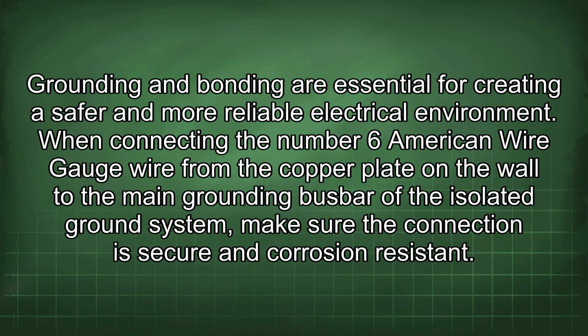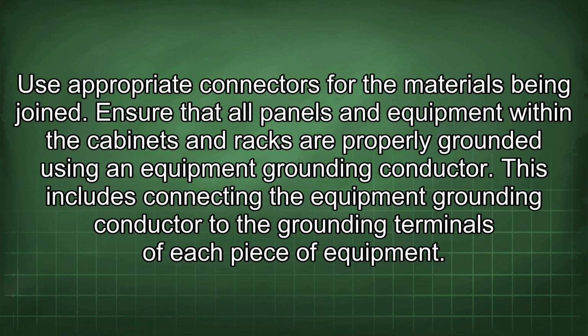When connecting the number 6 American wire gauge wire from the copper plate in the wall to the main grounding busbar of the isolated ground system, make sure the connection is secure and corrosion resistant. Use appropriate connectors for the materials being joined. Ensure that all panels and equipment within the cabinets and racks are properly grounded using an equipment grounding conductor. This includes connecting the equipment grounding conductor to the grounding terminals of each piece of equipment.